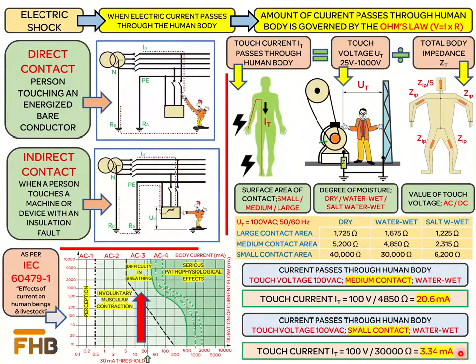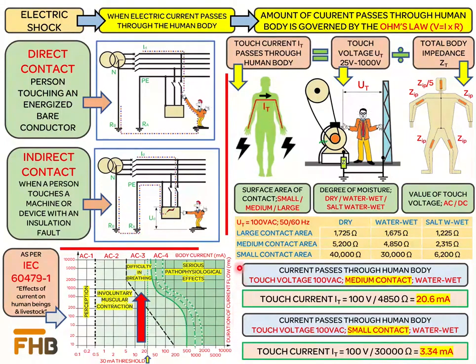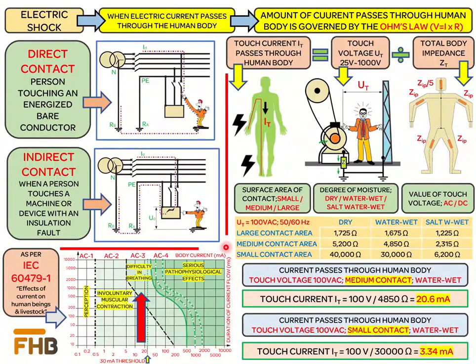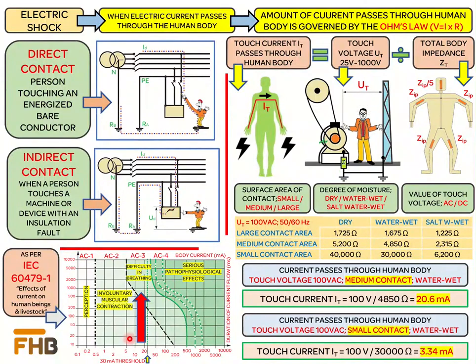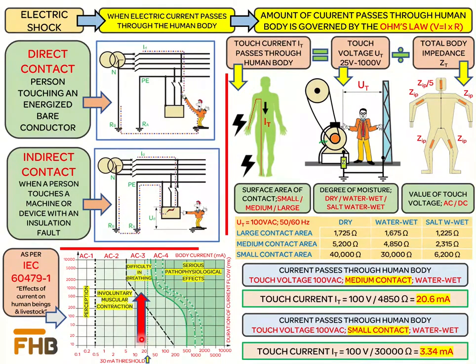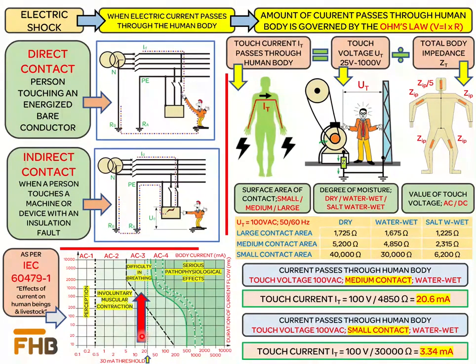As discussed earlier, the danger to a person from electric current mainly depends on the magnitude and duration of the current passing through the body. The time-current zone chart in IEC 60479-1 summarizes the effects of electric current on the human body, indicating the effects of AC current flowing from the left hand to the feet. All effects are highly dependent on current magnitude and its duration. From the chart, for the same amount of current the zone changes with increasing time duration, meaning the effects become worse as duration increases.